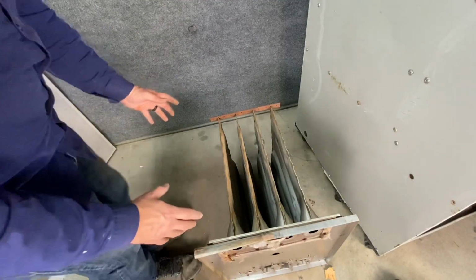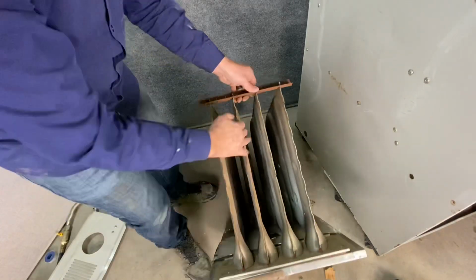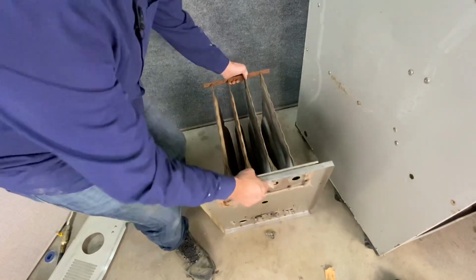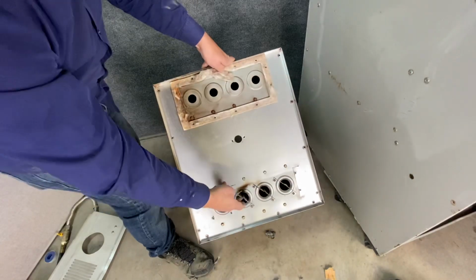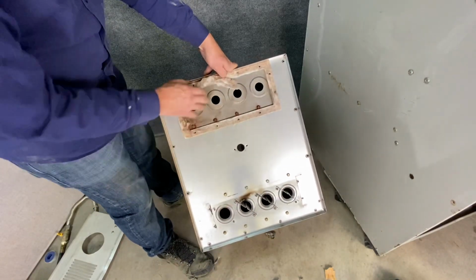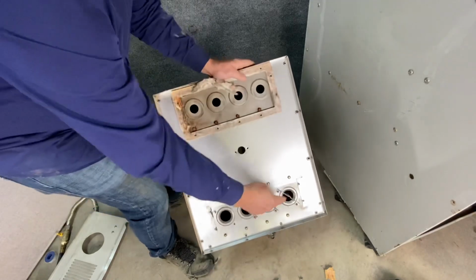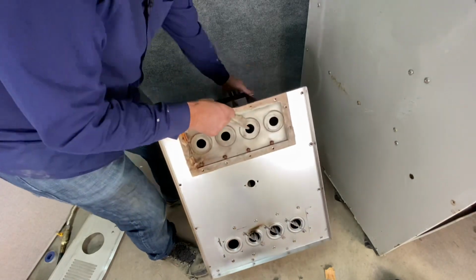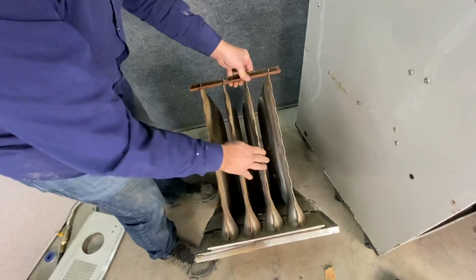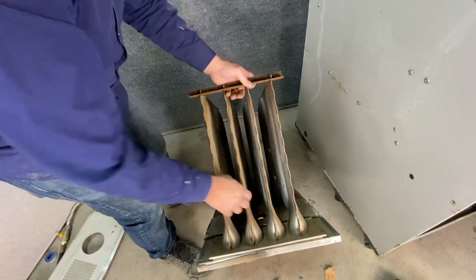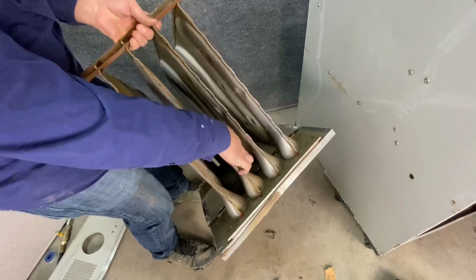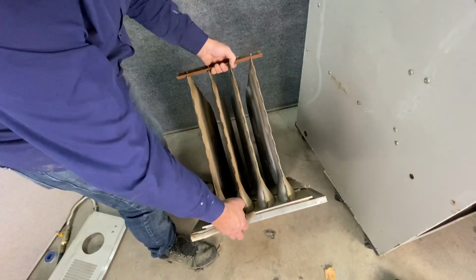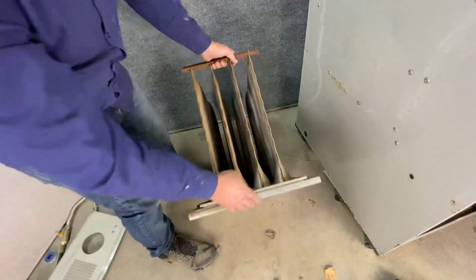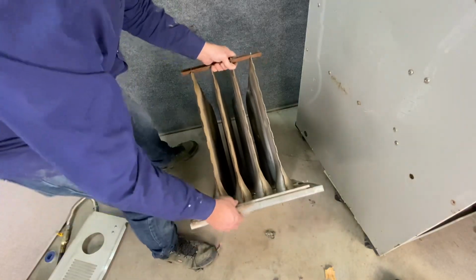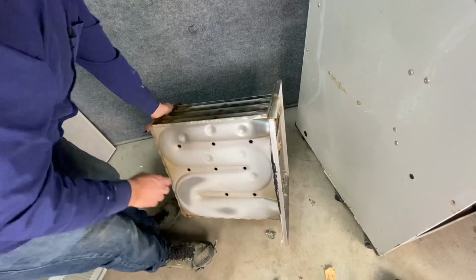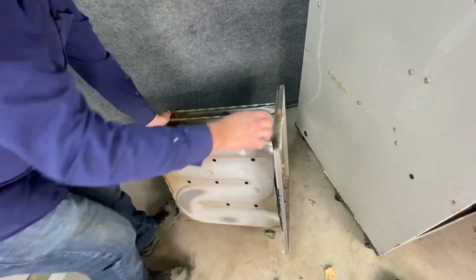And this is the heaviest part of the system. So this is our heat exchanger. The air moves on this side of the heat exchanger, and the burners and hot gases, flames go through the inside of the heat exchanger. So there were 4 different burners, so we have 4 individual heat exchanger tubes. You can see here the main limit switch went in the center. And as I move this around, I can hear a significant amount of rust. So that means that probably one of these heat exchangers was rusted out. So what I'm going to do is take one of these apart and see if we can find a damaged spot in here.